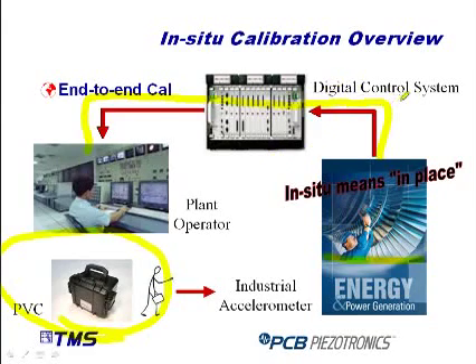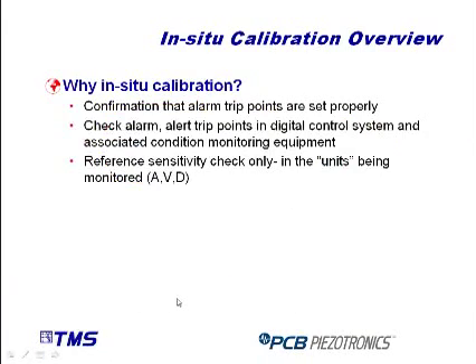So the digital control system would generally have signal conditioning. If it didn't, the signal conditioning would be in this chain as well. So we're not just calibrating the accelerometer, we're validating the entire measurement process. So we're confirming that the alarm trip points are set properly. We're checking these points in the digital control system and all the associated condition monitoring equipment. And we're able to do that in the units that are being monitored by that equipment, whether it's acceleration, velocity, or displacement. So the 9100D allows you to create a reference vibration signal in those units.